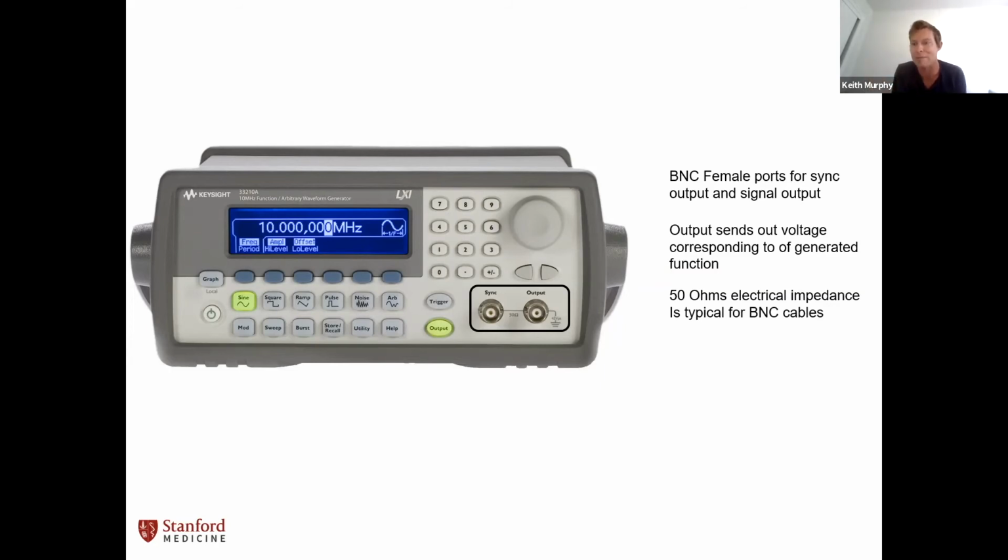And you can program a PRF, or pulse repetition frequency, using the function generator directly. No, actually, in ultrasound imaging, a burst is a single long cycle, a long pulse. It's not a repetition of pulses, but people have used the term where you repeat a number of pulses using the term burst. But now I can see why they used it because of this.